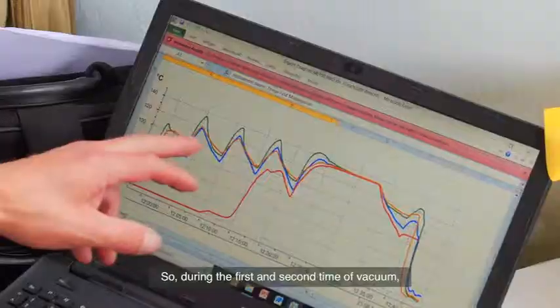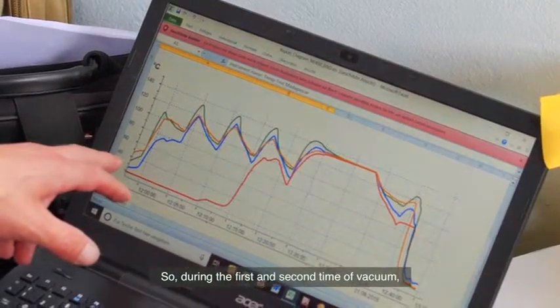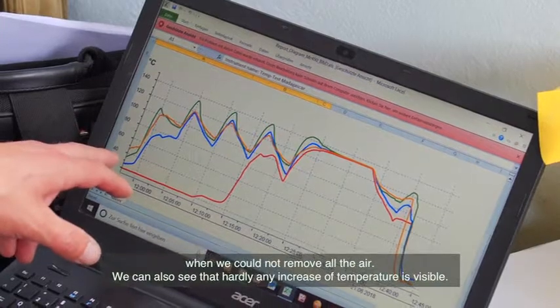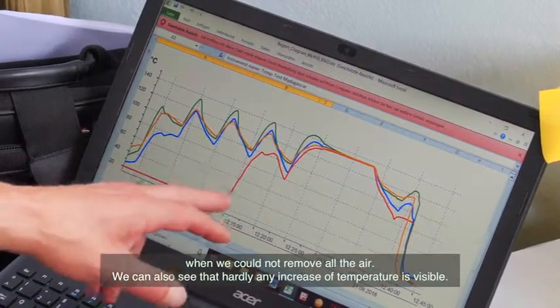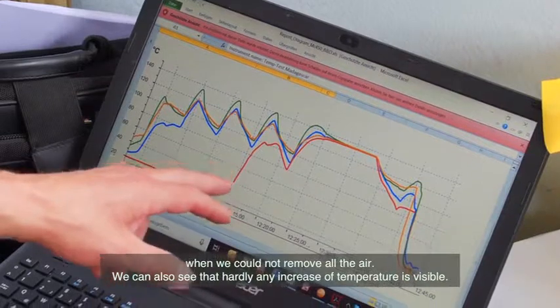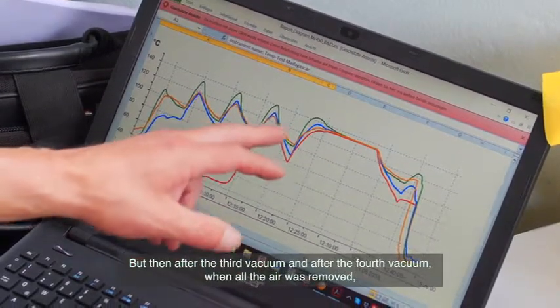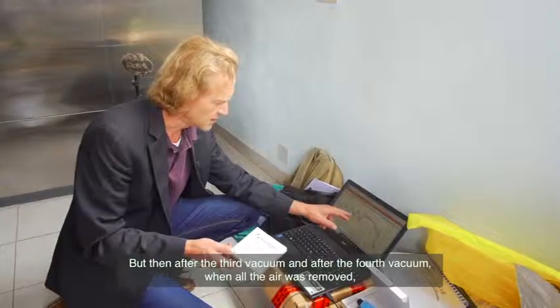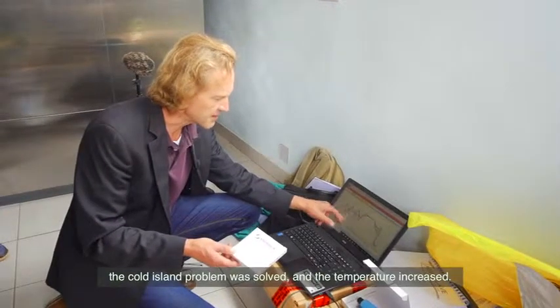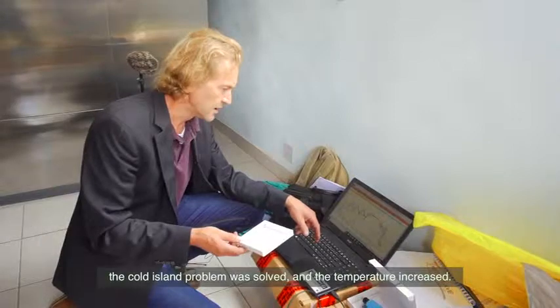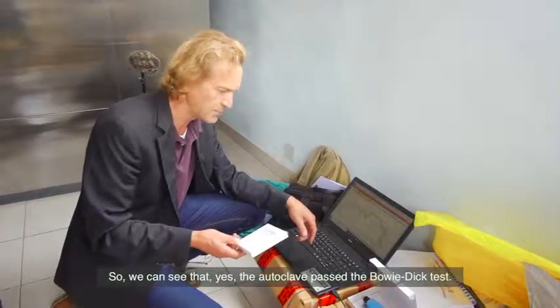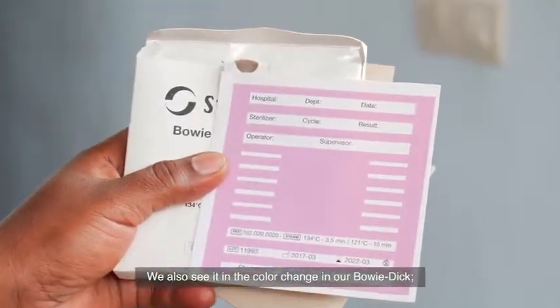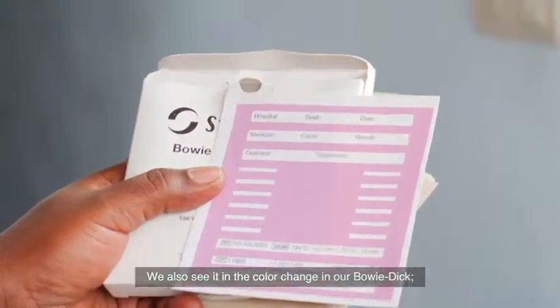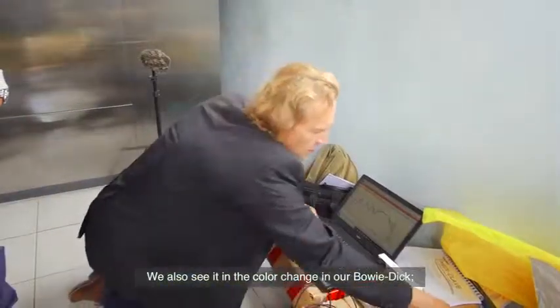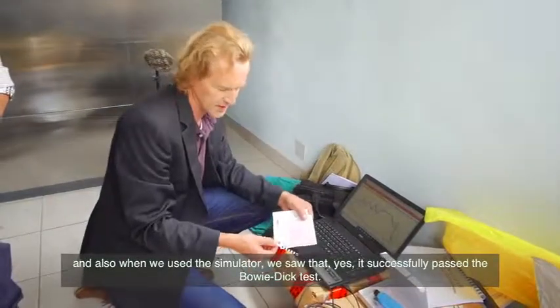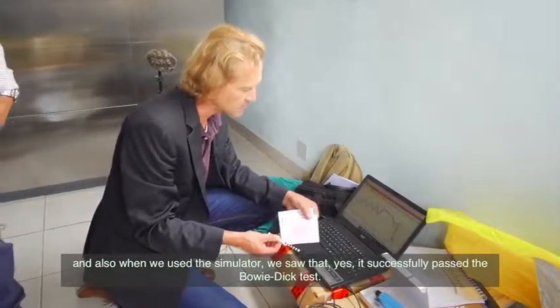So during the first and second time of vacuum, where we could not remove all the air, we also can see that hardly any increase of temperature is visible. But then after the third vacuum and after the fourth vacuum, when all the air was removed, the cold island problem was solved and the temperature increased. So we can see that, yes, the autoclave passed the Bowie-Dick test. We also see it on the color change in our Bowie-Dick, and also when we used the simulator, we saw that, yes, it successfully passed the Bowie-Dick test.